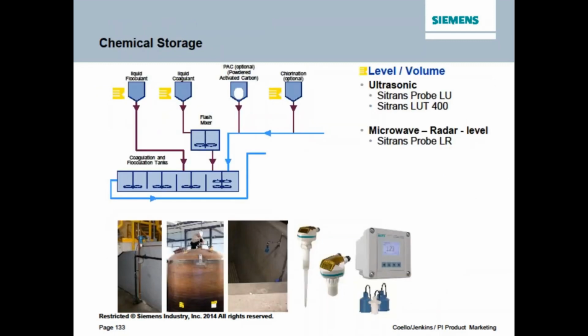Chemical storage, be it in a water, wastewater plant or an industrial plant, can really go either way. If you have a well-ventilated tank that keeps the vapor space inside the tank as air, ultrasonic can be a good technology for you. But if the tank doesn't have ventilation, or the ventilation doesn't work well, and vapors off-gas and build up inside the vessel, that's when we would want to go to radar for those chemical storage applications.